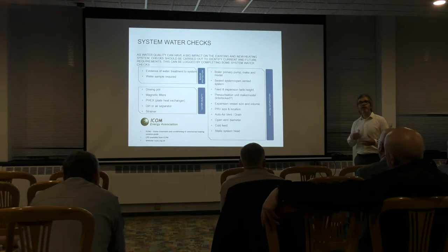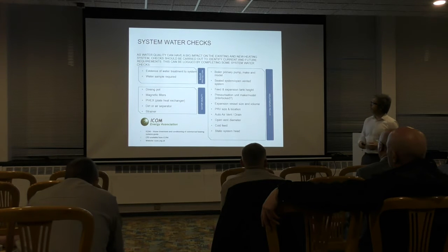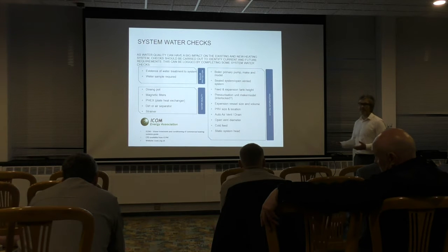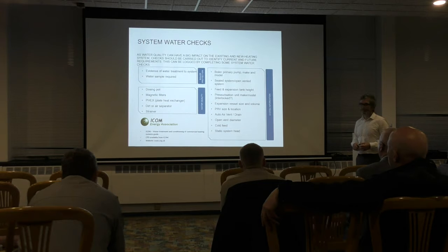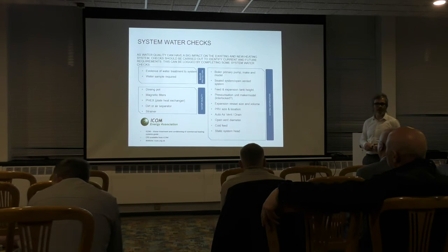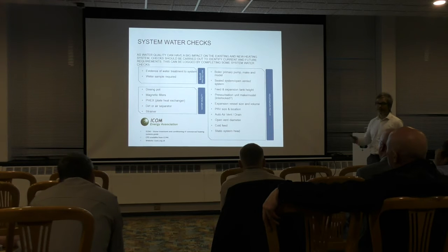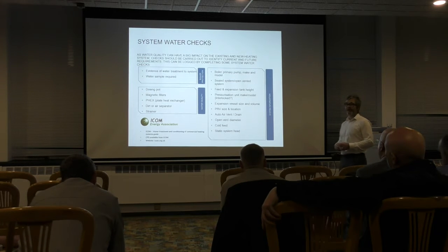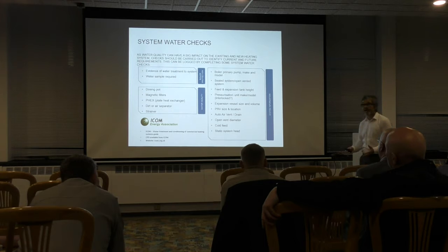But based on that, we can give guidance, or water treatment companies can give guidance, on really what water treatment you should be using on that particular site to protect those boilers. But things like hardware as well, things like dosing pots, and as standard practice to put those in, magnetic filters. I mean, water treatment companies have these kind of black magic voodoo magnetic filters that they claim work. They can never tell you how they work, but they do work. So yeah, put those in. Plate heat exchangers, I mean, we're seeing that more and more now. We're putting plate heat exchangers in to protect boilers.